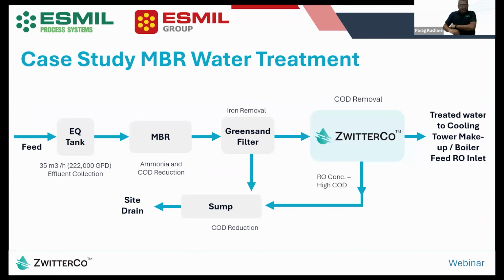So I've got the next case study, where XMBR water is treated with the RO system. Esmil here supplied a system to treat XMBR water to make it suitable for cooling tower makeup and to blend with the boiler feed RO system.